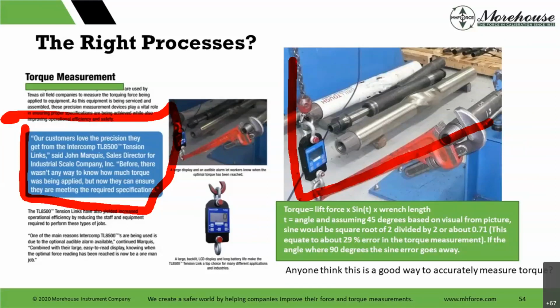And just by looking at this picture, I can tell you that the error, this is a 0.1% of full-scale device, something like that. I can tell you that we're not even near 0.1, 0.2, whatever the claim is. We're at probably 29% error. But hey, before there wasn't any way to know how much torque was being applied, but now they can ensure they are meeting the required specifications. I don't want to trust anything that someone is making measurements on like this, because I'm sure maybe an engineer budgeted for maybe 1 or 5% error, as they tend to do.